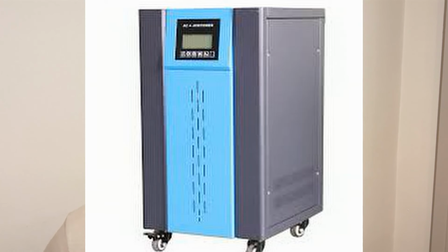Now, this costly mistake number 3 is something that is prevalent in Ghana, for reasons that I've explained on this channel a number of times. The ECG voltage quality, wrong voltage and surge protection. LED drivers are the sensitive part of the light fitting. This is why they fail a lot. You buy new fittings and after a couple of months you see 1 or 2 are not coming on.